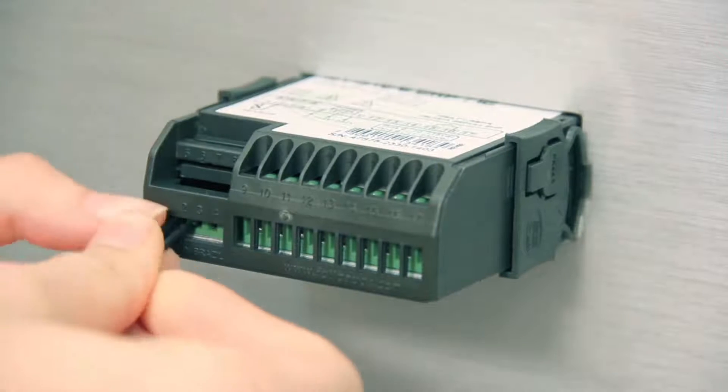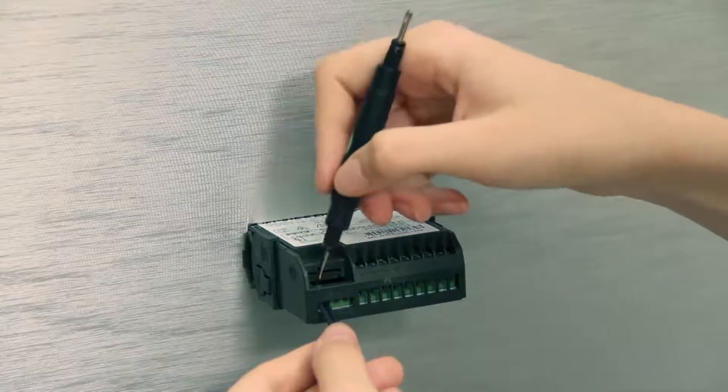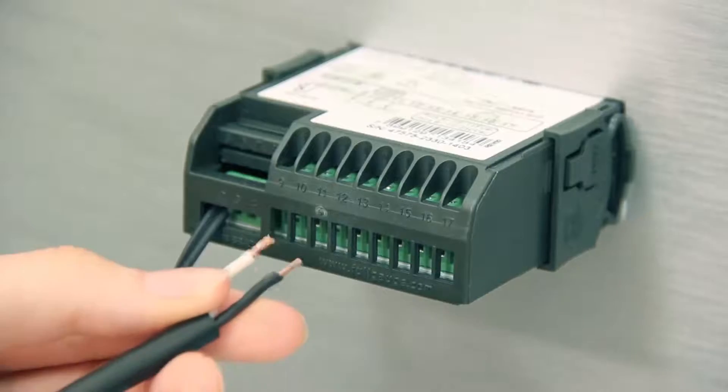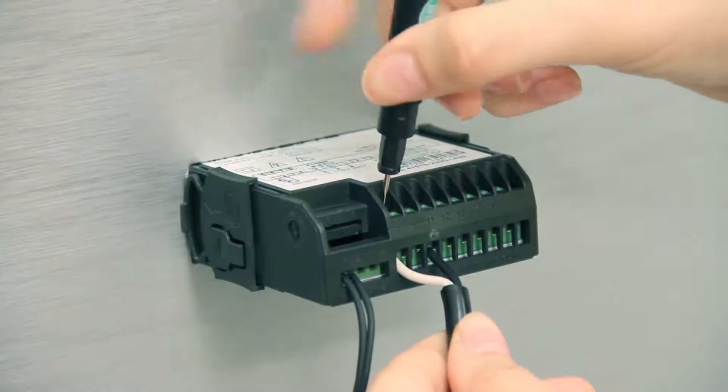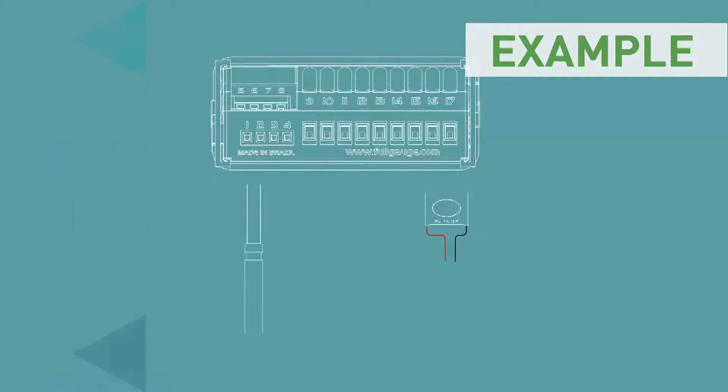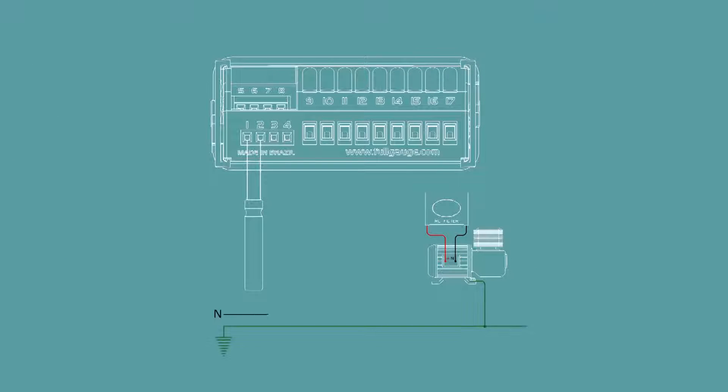We now present two installation examples of the MT512E 2HP. You must configure and install the instrument according to your needs. Cooling installation. Assuming power is less than 2 horsepower, a contact switch is not used. However, the RC filter is used. In this installation example, the supply is made with 127 volts AC.